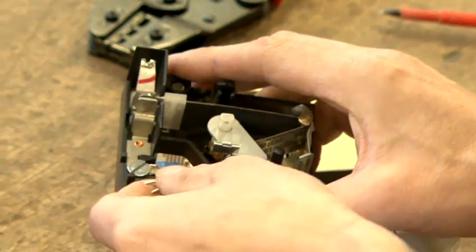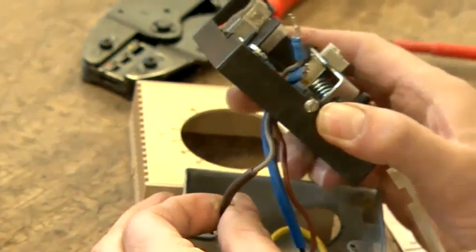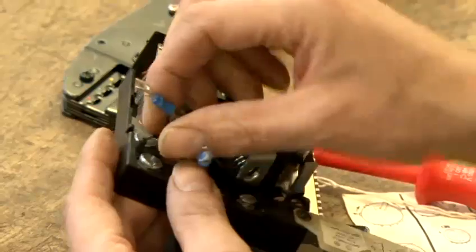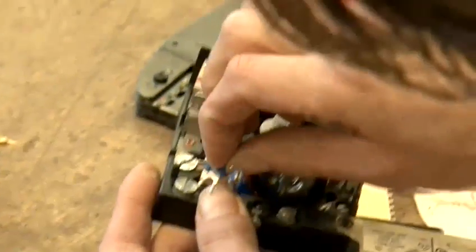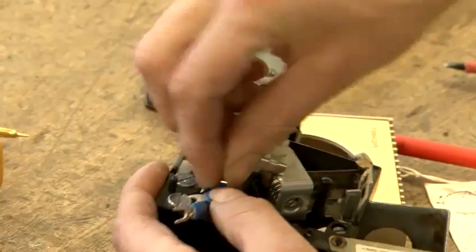Now my switched live, I've chosen the grey cable but I have oversleeved it with brown sleeving because it is a live conductor. This will go back and switch my heat pump when I'm calling for heating.